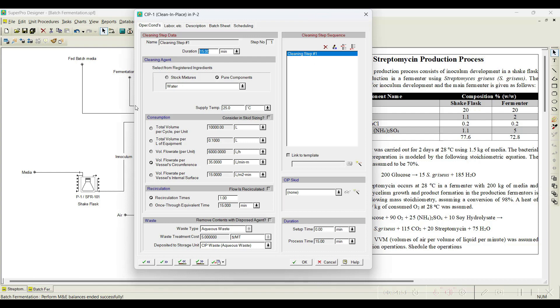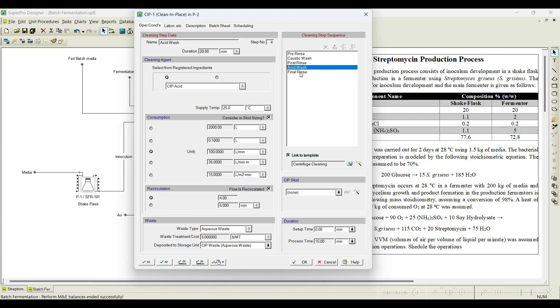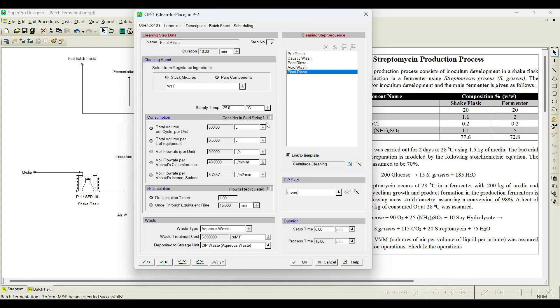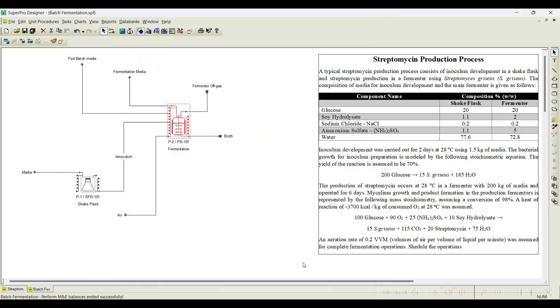When you add each step you need to define the flow rate and duration for that step. You can also go with a template — there are some templates available. Click 'link to template' and here you can notice several cleaning procedures. I will select 'centrifugation cleaning' and click OK. Once you select this, you can notice five predefined steps: pre-rinse with WFI water with a 10-minute duration, caustic stock mixture, post rinse, acid wash, and final wash. These components are already registered in the software. I will just use the default values available and click OK.